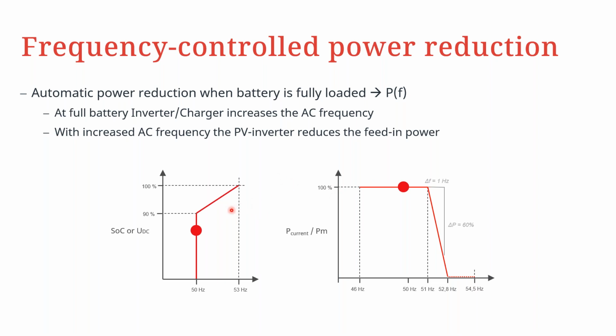So you could have a fully charged battery, but the load consumption during the day is quite high. And therefore, the Victron inverter is also able to balance the operating frequency that is required so that most of what is produced by the Fronius inverter is supplied directly to the loads. So this is then what we refer to as the optimal interaction between the Fronius and the Victron inverter by frequency drop.